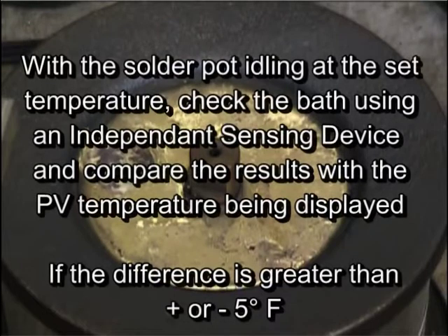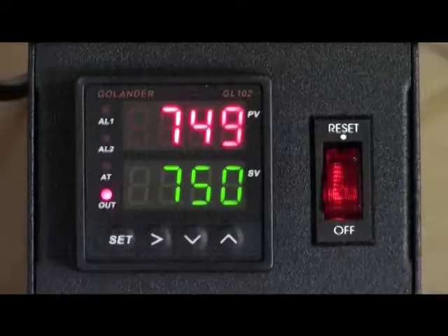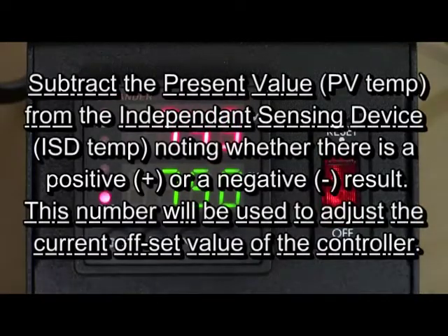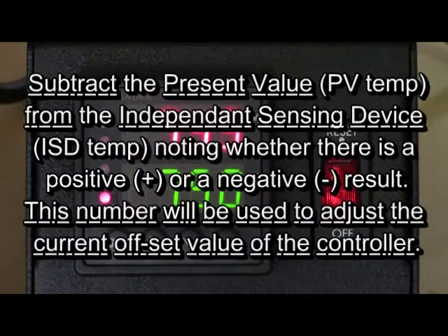Once your pot is stabilized and is idling at the set temperature, check the solder bath with an independent temperature sensing device and compare the results with the PV temperature displayed. If these temperatures differ more than plus or minus 5 degrees Fahrenheit, subtract the PV temperature from the ISD temperature, noting whether the variance is positive or negative, and save this number to adjust the offset value of the controller.